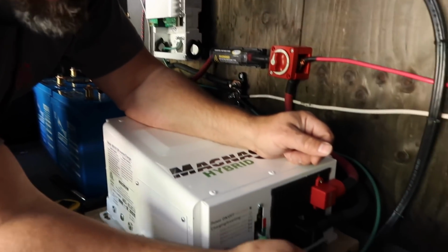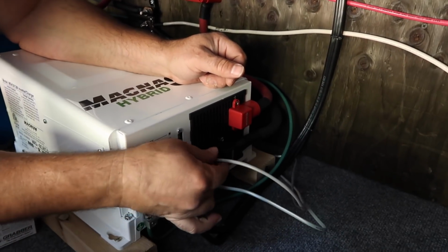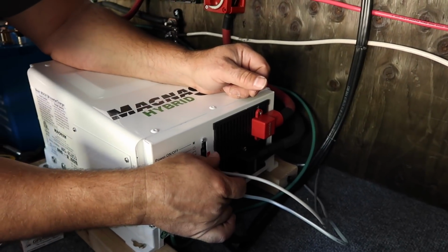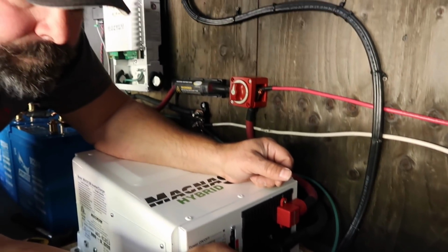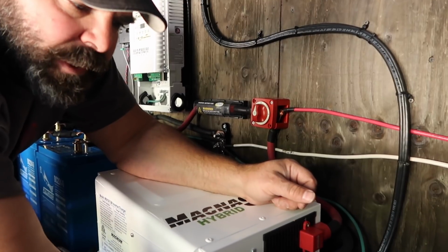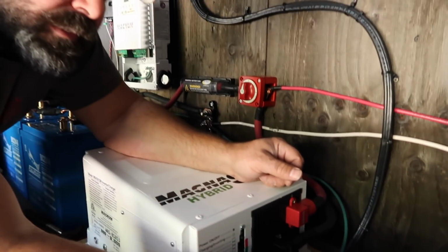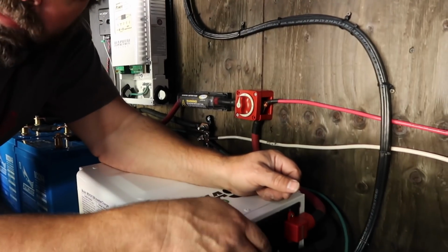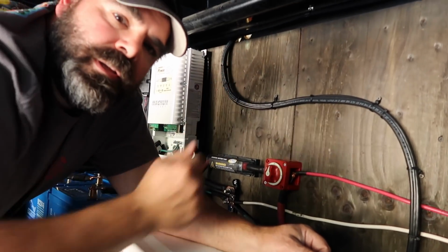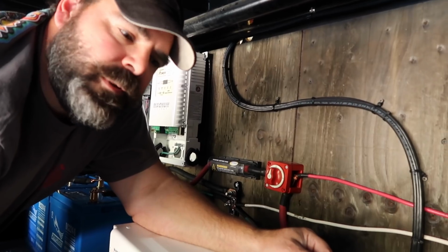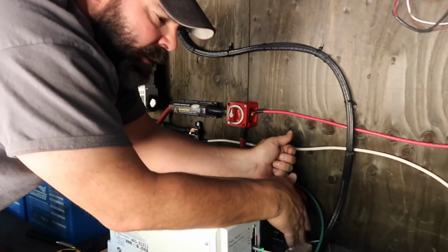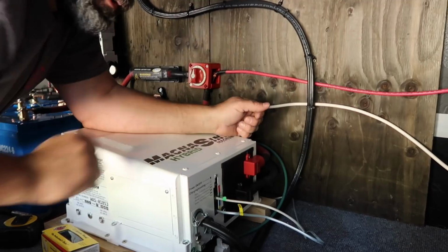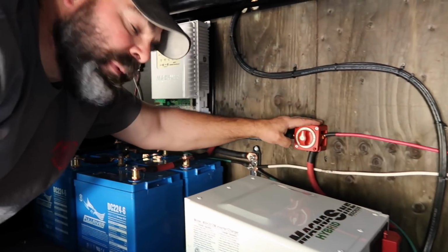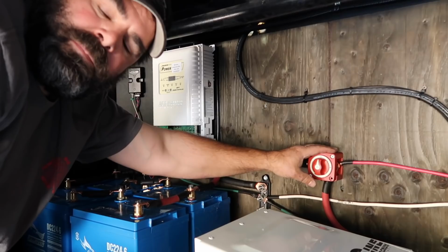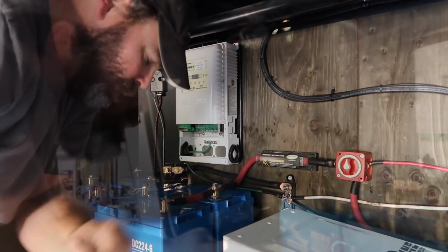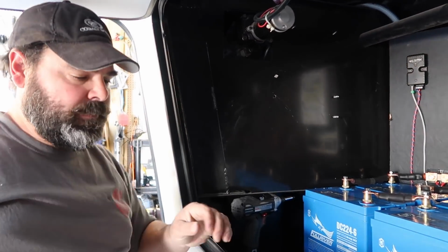We've got communication wires in here for the battery temperature sensor, and this other one is for the battery monitoring system. So temp sense and battery monitor right here. There'll also be another data cable plugged in that will go to the remote control up in the kitchen area of the fifth wheel. Also got the DC wired in, both positive and negative, all wired in. Main power still off though, so we're not energizing anything. Main power is off.